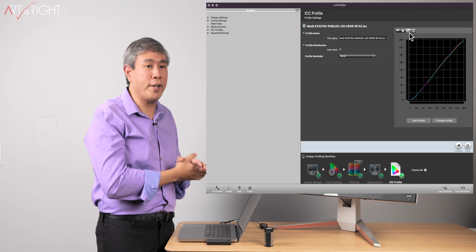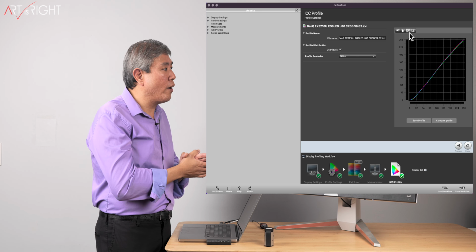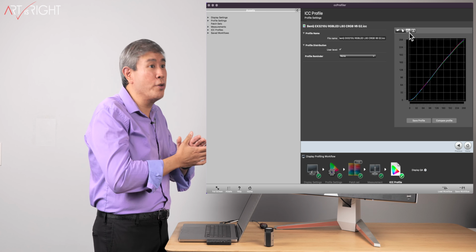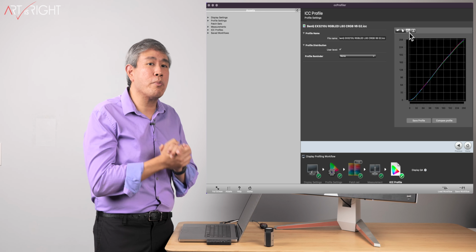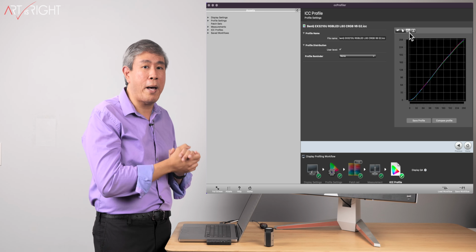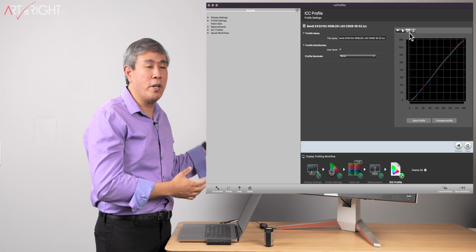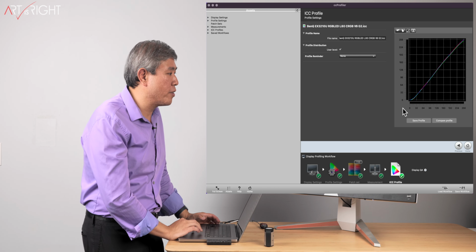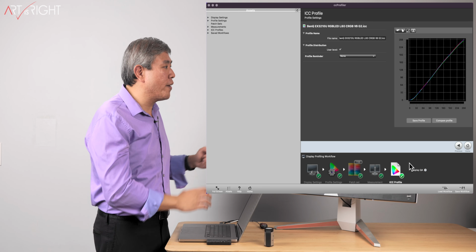In fact, the more overlapping it is, the better they are. However, if one starts to really diverge, or two start to really diverge out, that means you're probably not using the correct backlight matrix technology. So you want to go back and change that on your calibration. All right, now that we're done with this, I've saved the profile already.